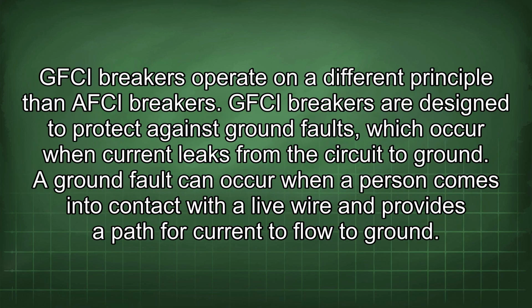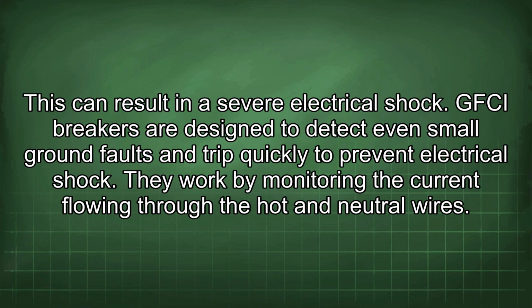GFCI breakers operate on a different principle than AFCI breakers. GFCI breakers are designed to protect against ground faults, which occur when current leaks from the circuit to ground. A ground fault can occur when a person comes into contact with a live wire and provides a path for current to flow to ground. This can result in a severe electrical shock.